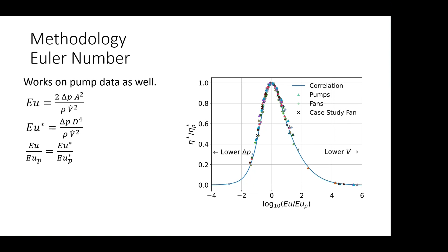The original authors only applied this to fans, but the Euler number isn't defined with any assumption about the medium. In the Buildings library, we handle fans and pumps with the same model, so there's no reason it shouldn't apply to pumps as well. We tested the data we have for pumps and plotted it against this curve, and the pump data also follow it pretty well — so we think it should be applicable to pumps too.